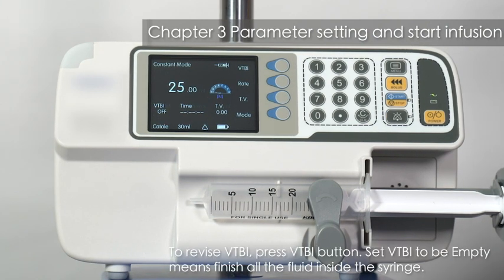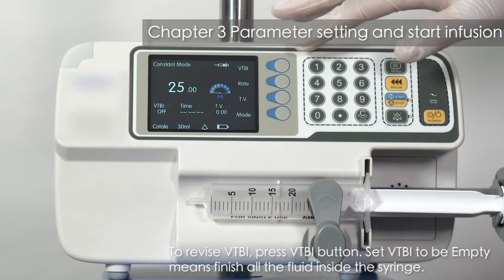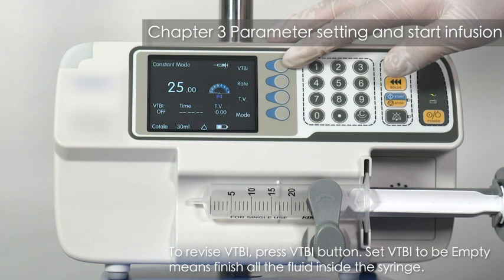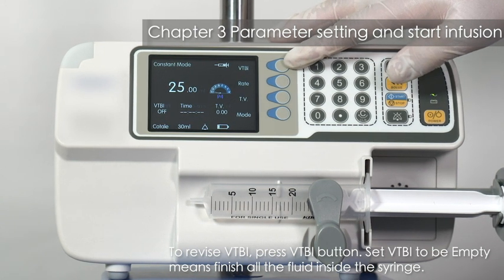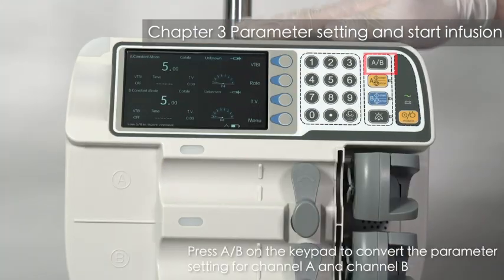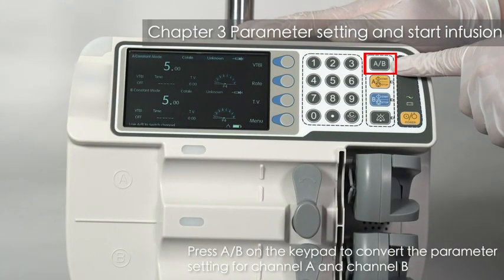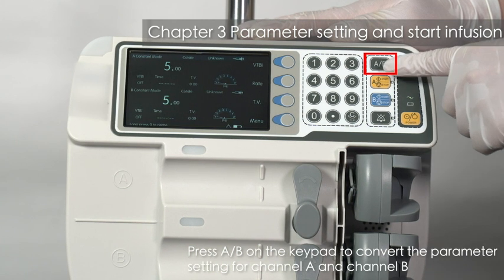To revise VTBI, press VTBI button. Set VTBI to be empty, which means finish all the fluid inside the syringe. Press A/B on the keypad to convert the parameter setting for channel A and channel B.